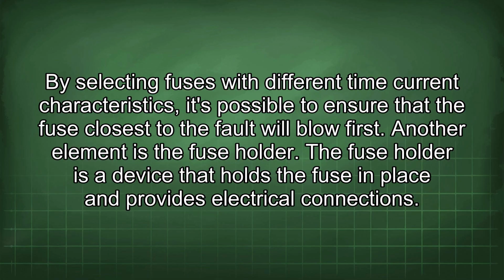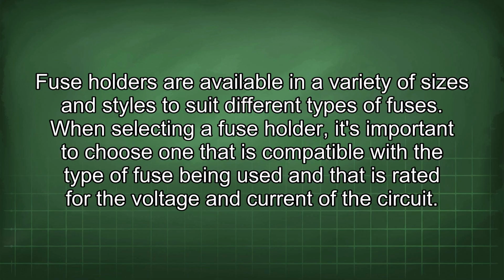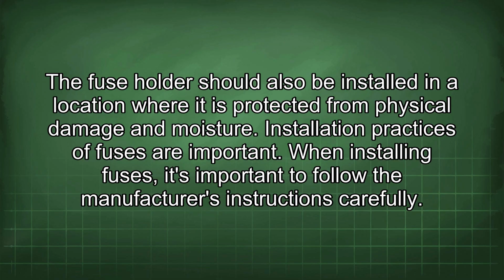Another element is the fuse holder. The fuse holder is a device that holds the fuse in place and provides electrical connections. Fuse holders are available in a variety of sizes and styles to suit different types of fuses. When selecting a fuse holder, it's important to choose one that is compatible with the type of fuse being used and that is rated for the voltage and current of the circuit. The fuse holder should also be installed in a location where it is protected from physical damage and moisture.